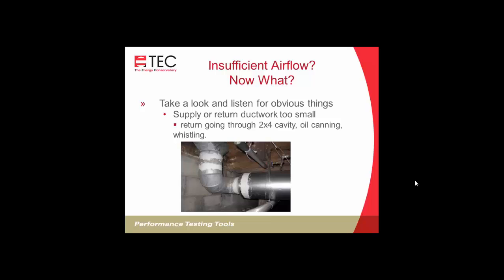And you may be able to see some pretty obvious things. One of the common things you might see is a return air duct going through a crawl space and coming up through a 2x4 cavity. So now you've restricted that duct. Maybe it's two stud cavities wide, and it's tall enough, but where your central return filter is, maybe that's big enough, but it's only 3.5 inches deep. So that really is a restriction, and you may be seeing 100 pascals or more of resistance because of the airflow going through such a small cavity, and it might need to be enlarged, up to 8 or 10 or even 12 inches deep in order to get enough airflow through that center return.